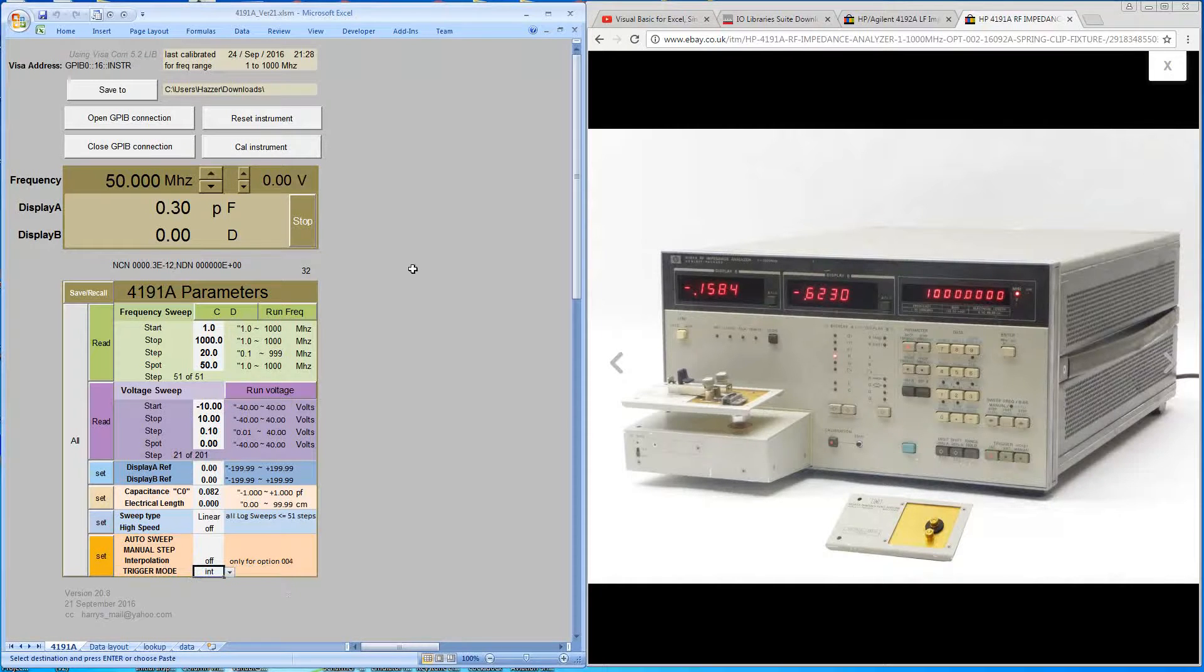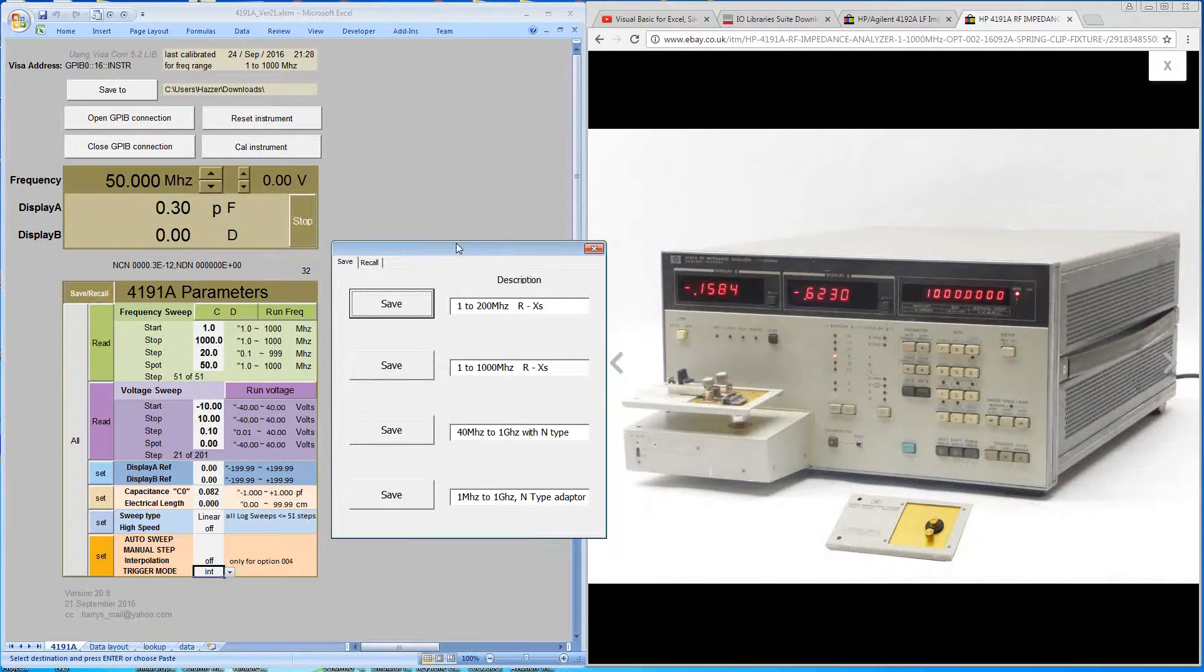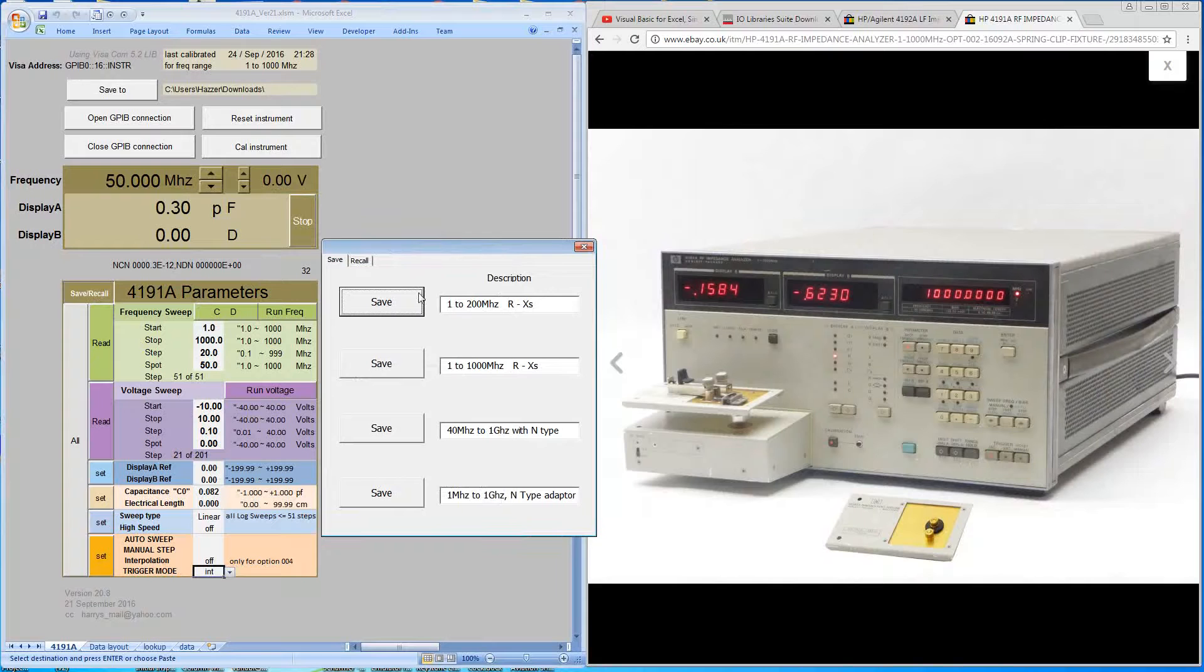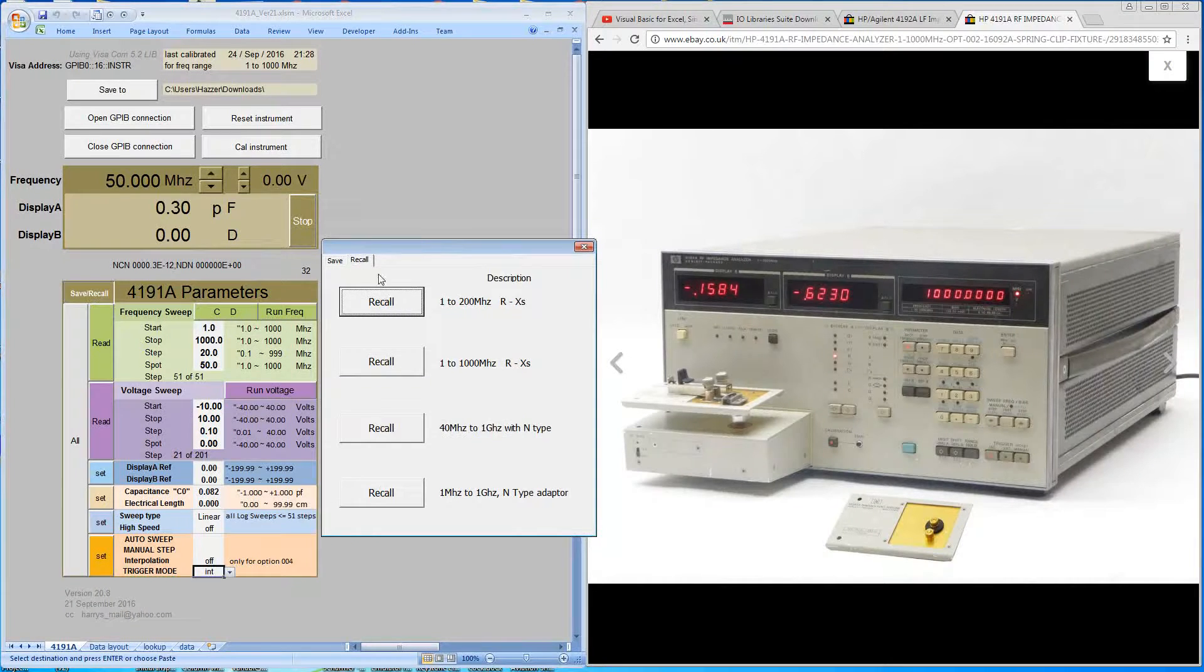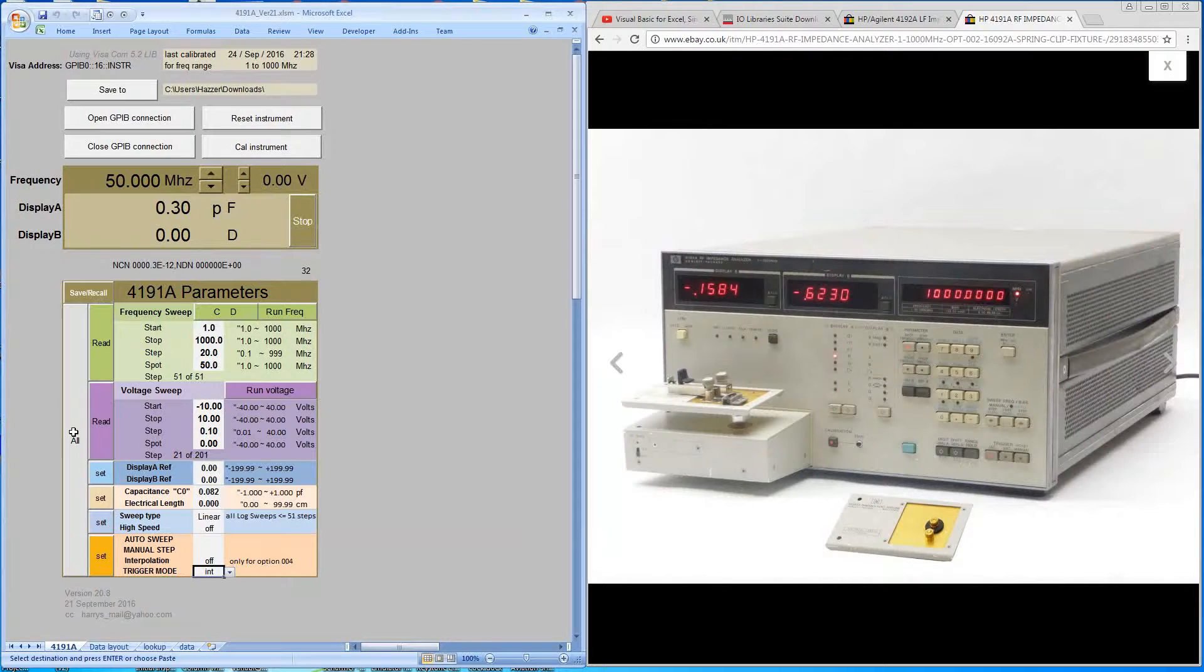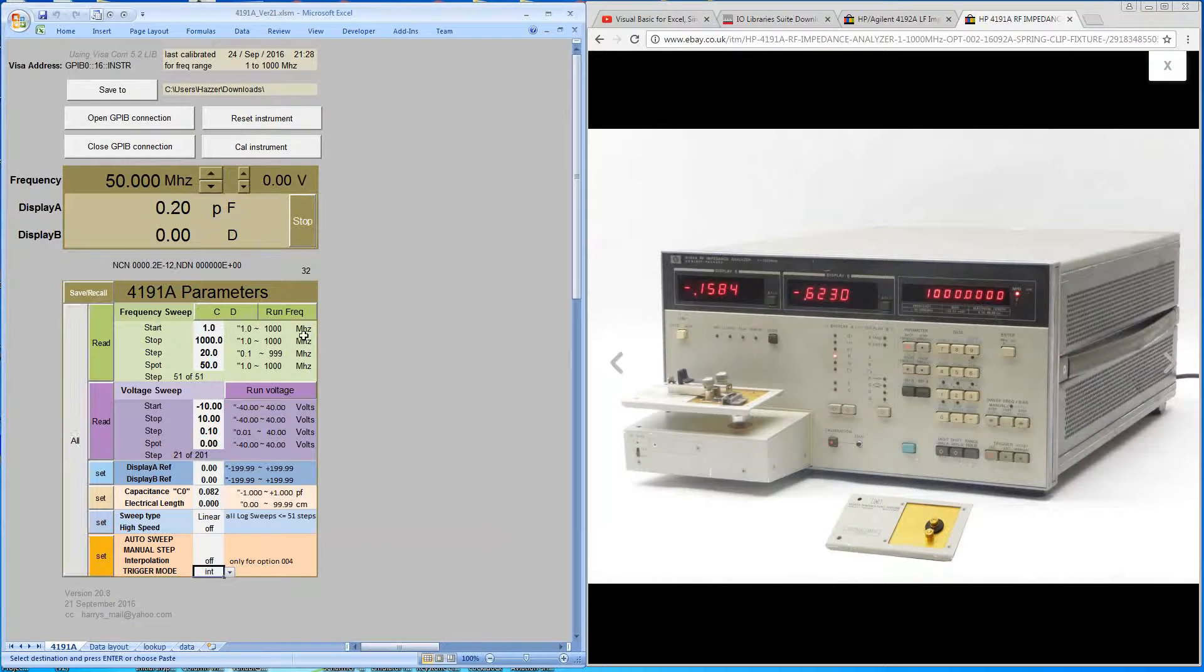So you can alter any of these parameters and you can save them within the software package in one of four locations. And you can give it your own name to define it. And then any time you can recall that to the front panel. Once you've recalled a number of settings, you can send them to the machine by hitting the all button. And the machine is now configured as for this front panel here.